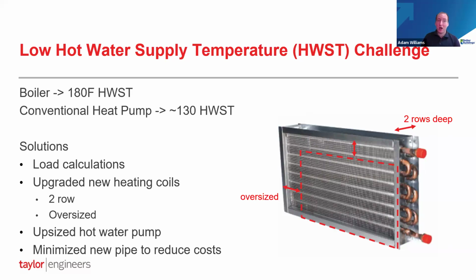The next thing we did was we were already planning on replacing the reheat terminal units. So we said, well, let's upsize those terminal units because we're already replacing them. Let's make them have as much capacity as possible. The way we did that, we increased the rows, the depth of the heating coils. You can generally get heating coils as 1 row, 2 row, or 3 row, typically. Let me mark this up so that it's clear. We're talking about the depth of the coil here. And when you're at a building, you can generally see these tube bends. This is a photo of a 2-row coil, which is what we ended up going with in most cases.